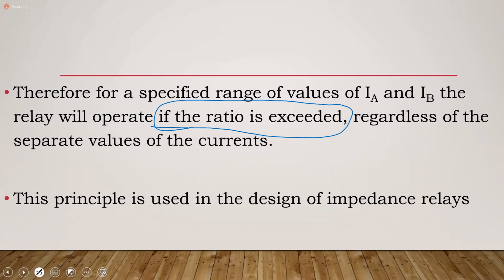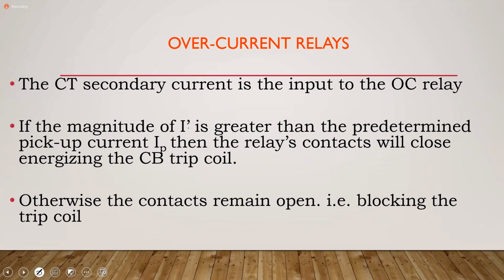Okay. So as I said earlier, we want to spend a little time looking at the overcurrent relay, and run through a little exercise with it. For your overcurrent relay, we have already established that your current transformer is the input to your overcurrent relay. And overcurrent here simply means that it will operate once the preset current is exceeded. But it is not a straight operation in terms of what comes in. But we'll go through and we'll see how this works.